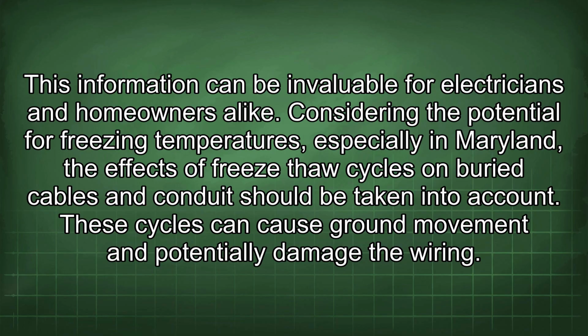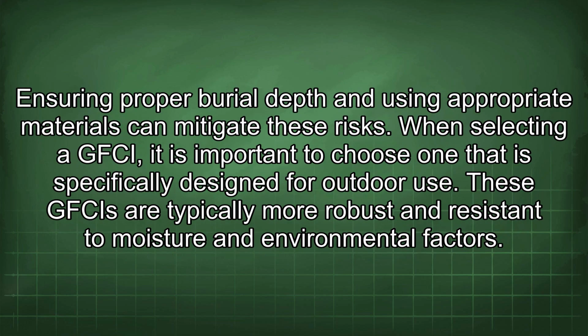Considering the potential for freezing temperatures, especially in Maryland, the effects of freeze-thaw cycles on buried cables and conduit should be taken into account. These cycles can cause ground movement and potentially damage the wiring. Ensuring proper burial depth and using appropriate materials can mitigate these risks.